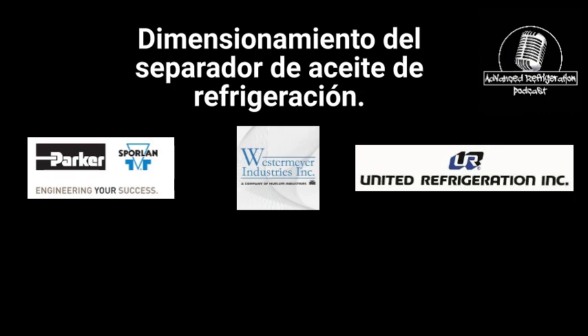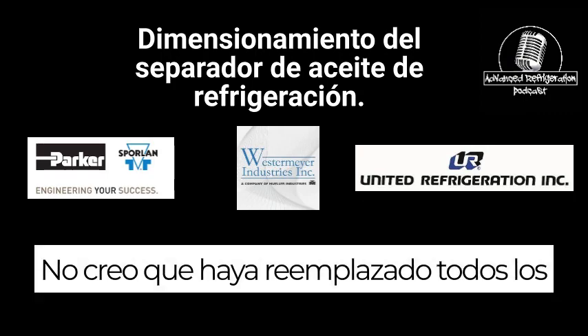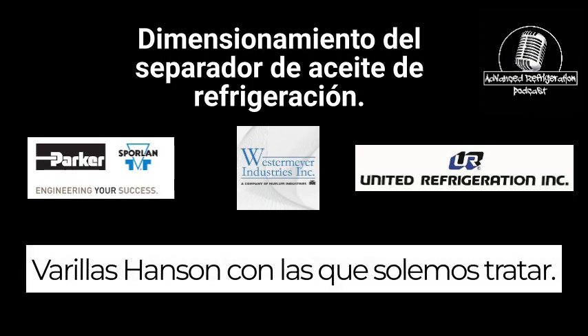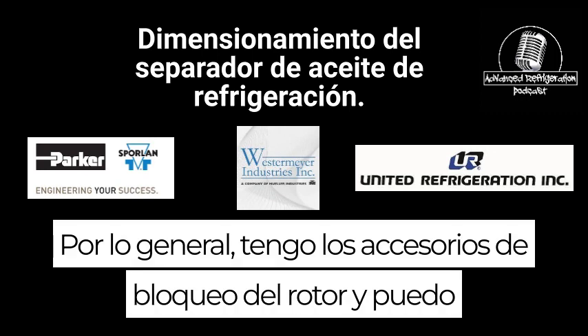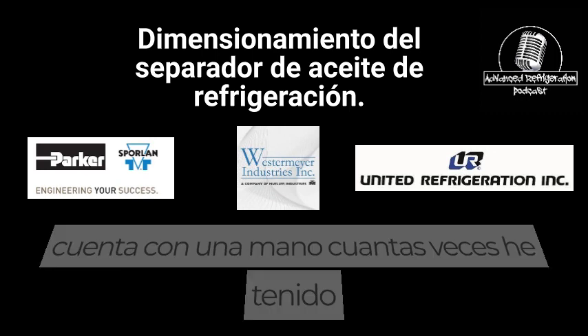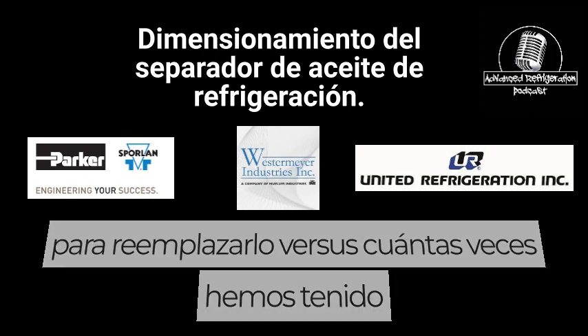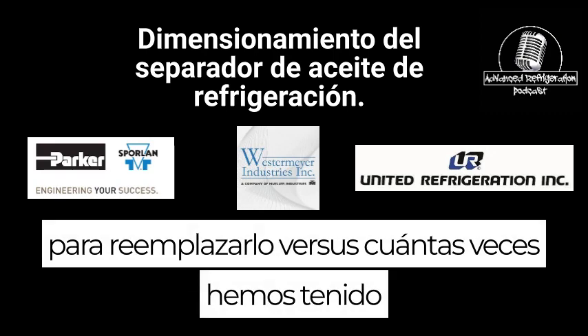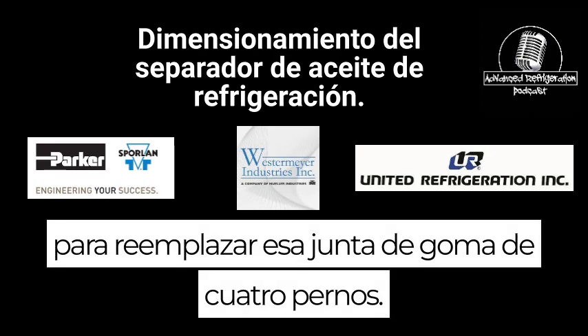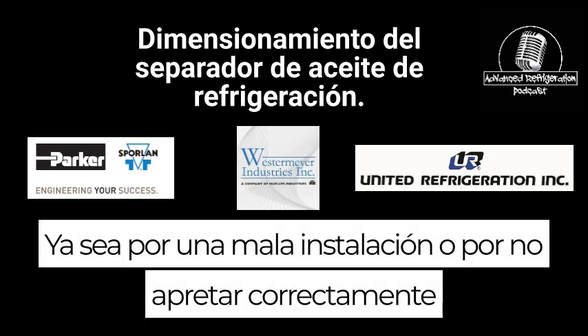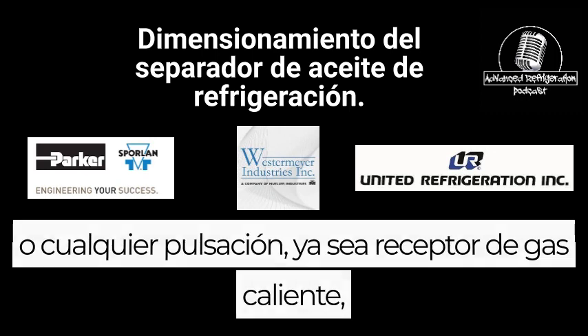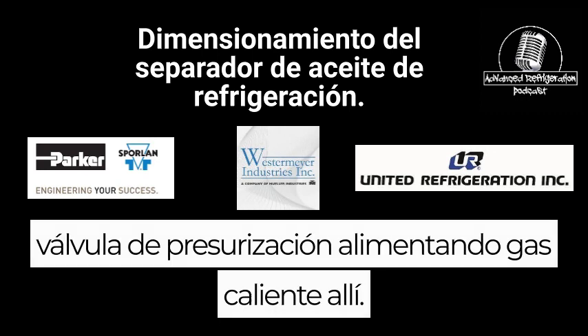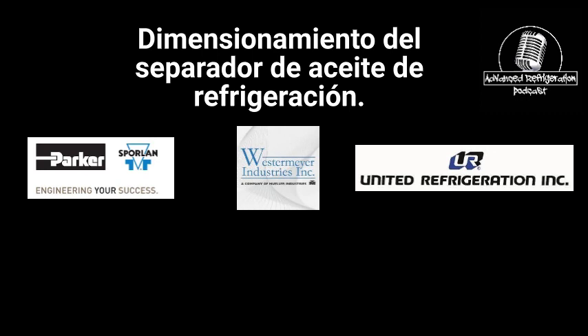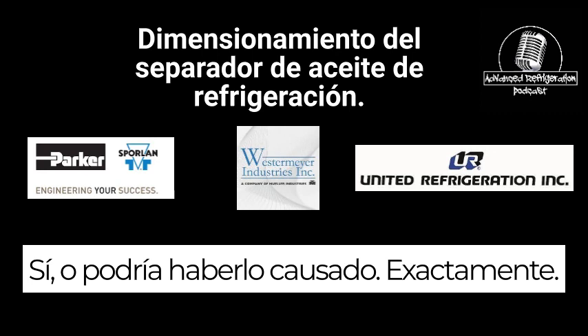I don't think I've ever replaced one. The Hansen rods that we usually deal with have the Rotolock fittings, and I can count on one hand how many times I've had to replace it versus how many times we've had to replace that 4-bolt rubber gasket, whether it be poor installation, not torqued properly, pulsation, or a receiver pressurization valve feeding hot gas in there. Yep. Whatever might have caused it, exactly.